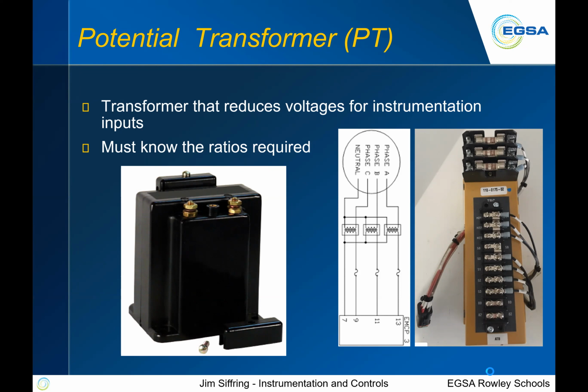Obviously, the device on the right, the yellow one, is a Caterpillar one. It's a Cat CT or a PT, excuse me. Graphically, you'll see it in the middle schematic there, where you're looking at phase A, phase B, and phase C, and neutral, and how it's wired into some transformers. Those transformers can go through some fuses, which you'll see at the top of that device, and it goes into the controller itself. Another on the left is just another universal type part.